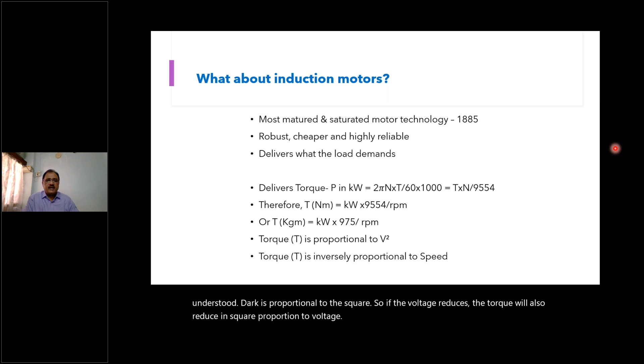Similarly, the relationship between torque and voltage also has to be understood. Torque is proportional to V square. So if the voltage reduces, the torque will also reduce in square proportion to voltage. Similarly, the relationship between torque and speed also has to be understood. Torque is inversely proportional to speed. As the speed decreases, the torque will increase. One slide is there where I am trying to take you to understand how it works.